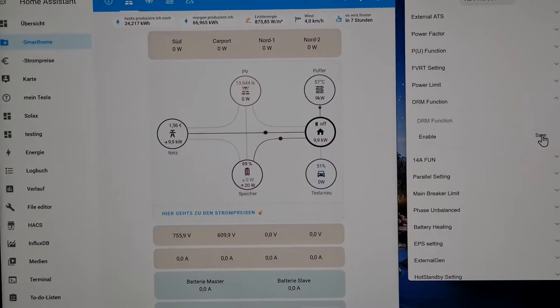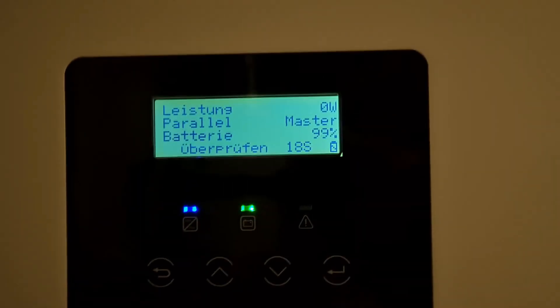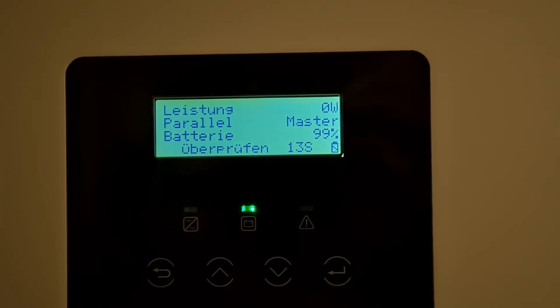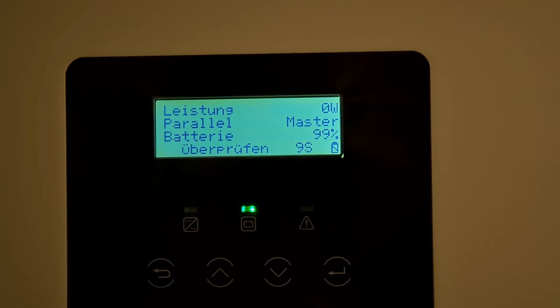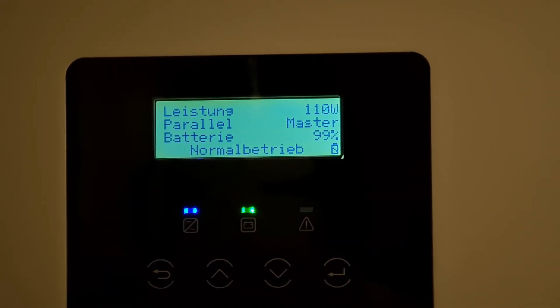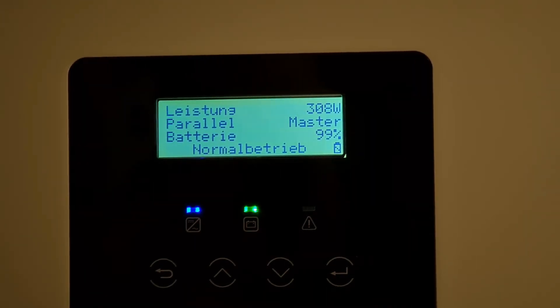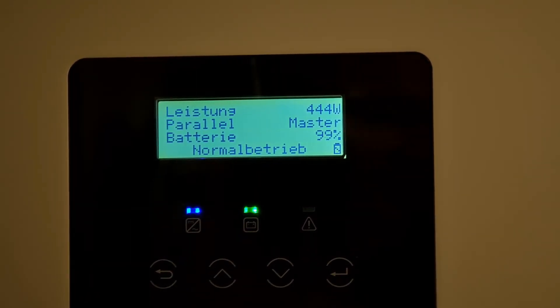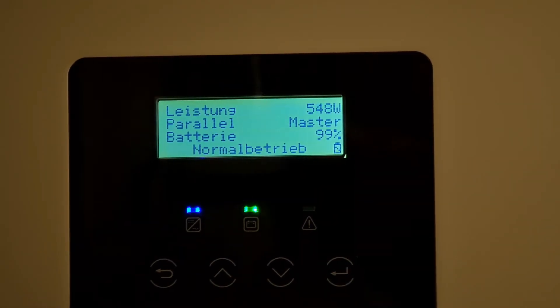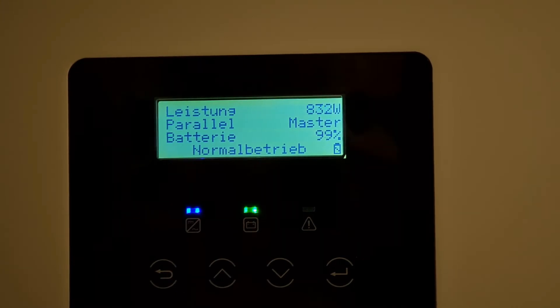As you can see, I'm now disconnecting it from the mains. Why I need 9 kilowatts right now, I don't know — my buffer probably switched on. Now it will take another 15 seconds and then it should start up normally in regular operation. With the DRM function enabled, the regulation of the MPP trackers to the maximum power point takes a bit longer than when the function is disabled. But once all MPP trackers have ramped up, the system runs exactly the same as when the function is deactivated.